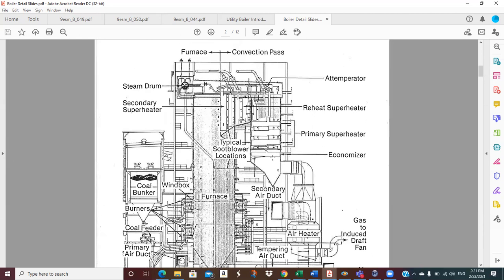So this probably does a better job of showing our different heat transfer sections. The secondary superheater sees the hottest gases out of the furnace. And then we get a reheat superheater, then a primary superheater, and then an economizer. So your feed water from your highest temperature feed water heater is pumped through the economizer to boost it one more time, and then it goes to the steam drum.